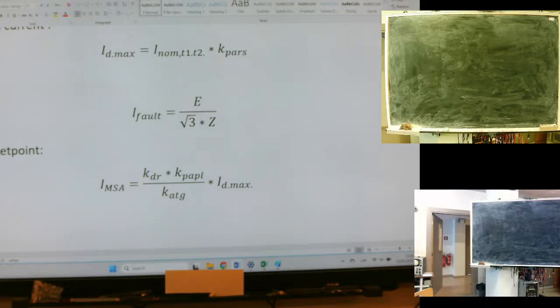So, once more time, the logic is very simple. We want to have the lowest possible set point to be sure that we will detect the fault current. But at the same time, we need to check and to see how this relay will operate when we will have the real fault. Of course, this is paper, this is just calculation, we don't have a real fault, but we could calculate the real fault current value. That's why the last step is to check our set point. Is it good or not?